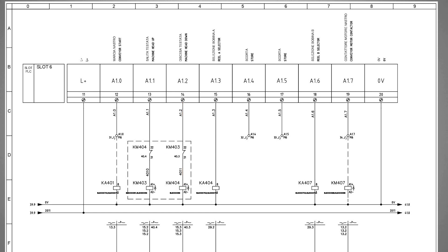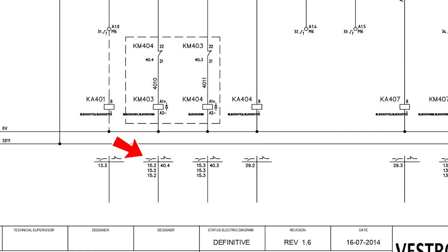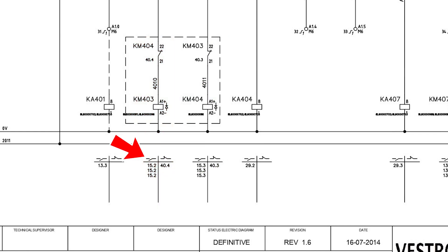will turn on KM404 through the normally closed contact of KM403. This means both contactors KM403 and KM404 are interlocked with each other, and only one contactor can be turned on at once. The NO and NC contact symbols along with the page number are mentioned under the coils of these contactors. The wiring for the normally open contacts is mentioned on page number 15, column number 2 and column number 3.